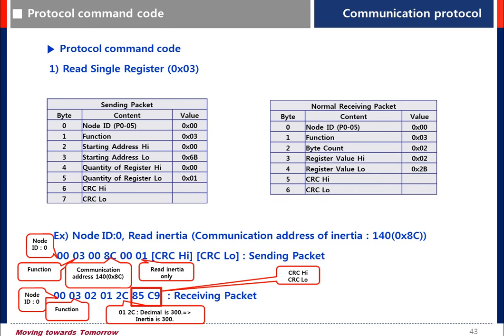Let's see the protocol command code. Refer to the sending packet table. In this example: 00 is the node ID, 03 is the function code, 008C is the starting address (high and low), and 0001 is the quantity of registers.